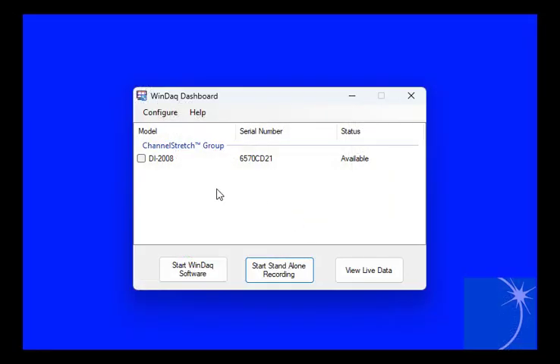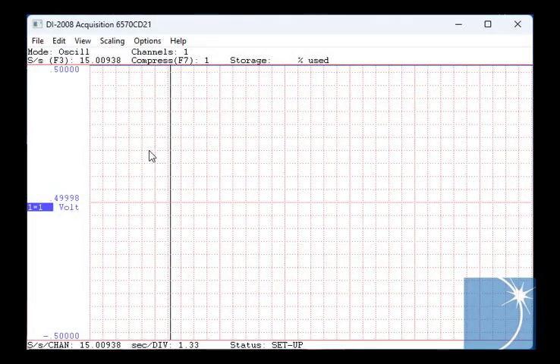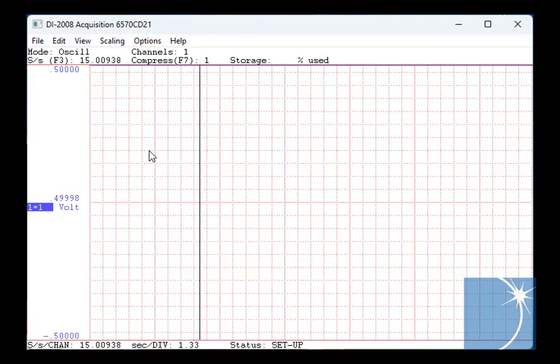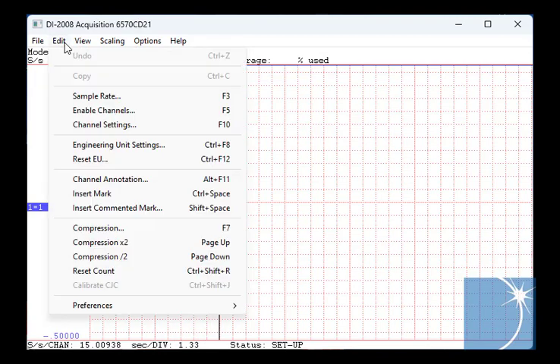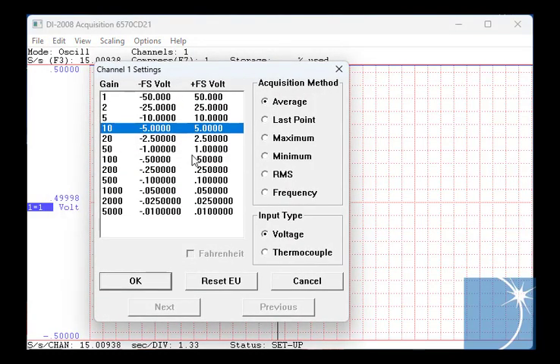With the transmitter connected to the DI-2008, we'll run the WinDaq dashboard and start WinDaq. Note that the default measurement range is plus or minus a half a volt. Since we'll drop 1 to 5 volts on the 250 ohm shunt resistor, we'll change the gain to 10, or plus or minus 5 volts full scale.